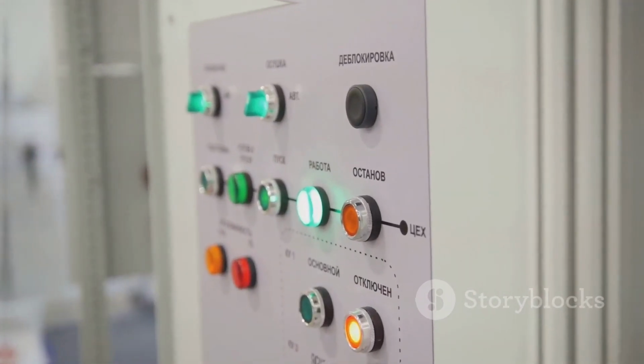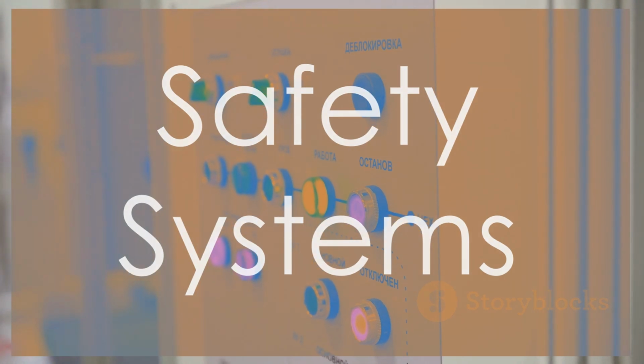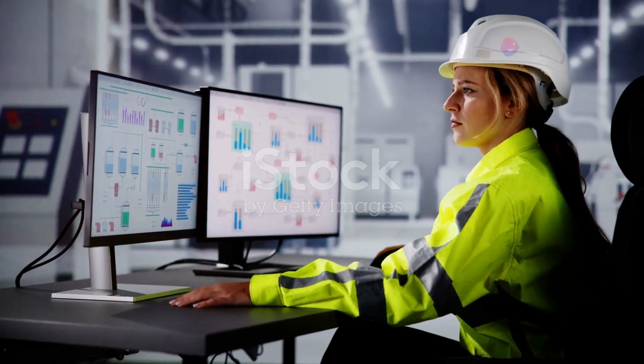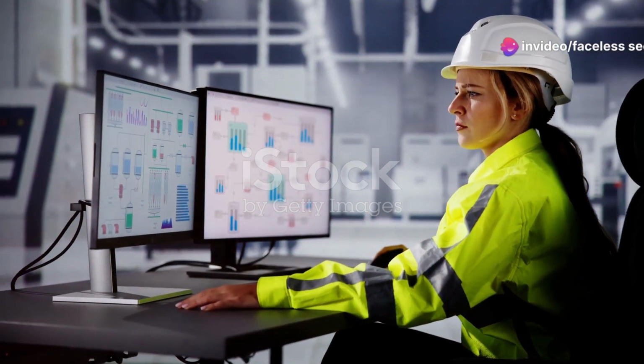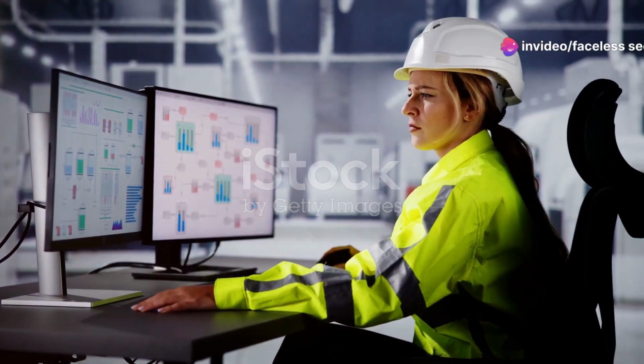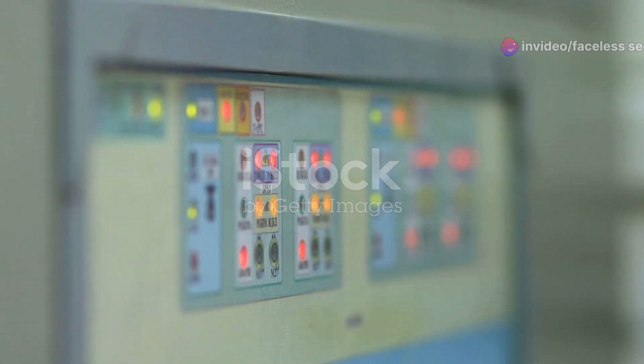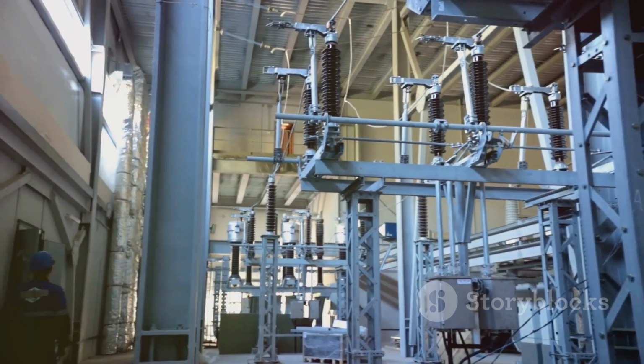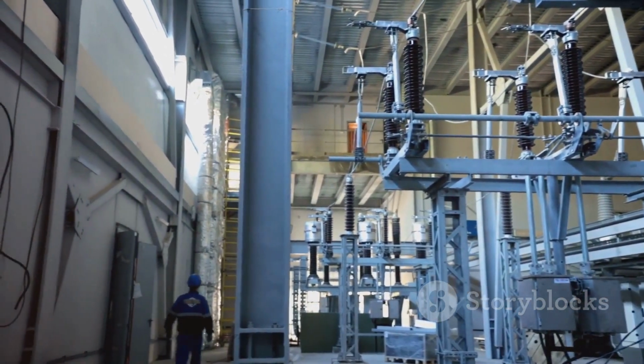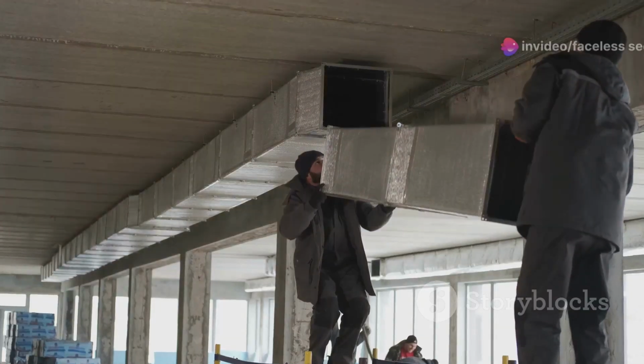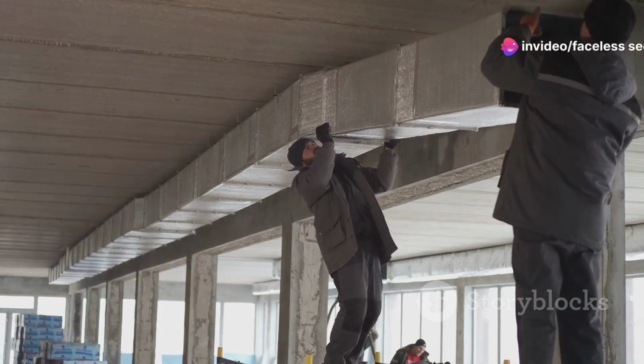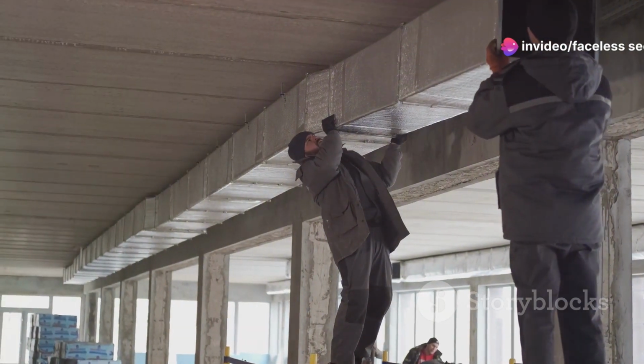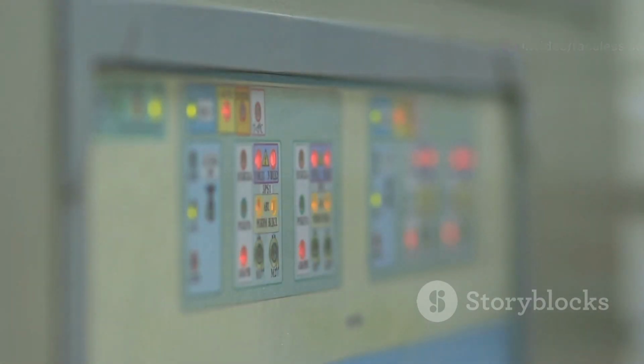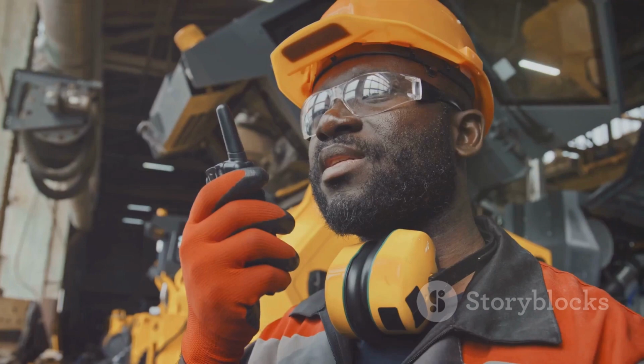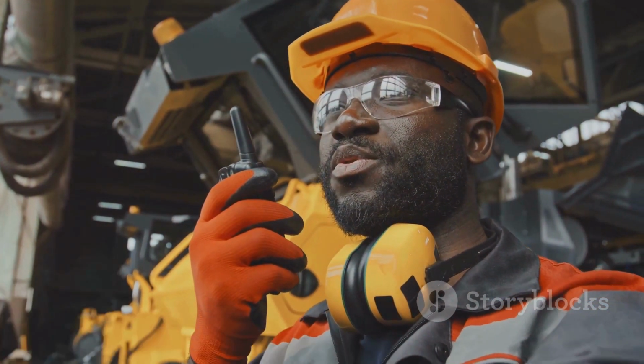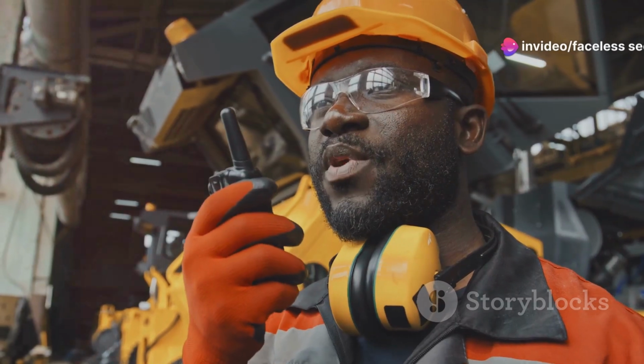industrial systems. Safety systems are the guardians of industrial operations, providing critical protection to processes, equipment, and personnel. In the event that a process exceeds its allowable control parameters, these systems step in to prevent harm, even if it means halting production temporarily. While this might lead to a loss of productivity, it ensures the safety of equipment and human lives. Traditionally, safety systems are designed to operate independently from the control systems they protect, though they often share some communication channels, field devices, and alarm systems.